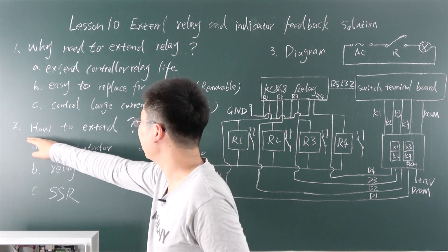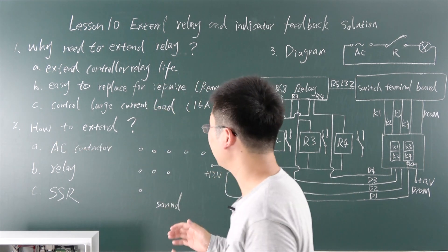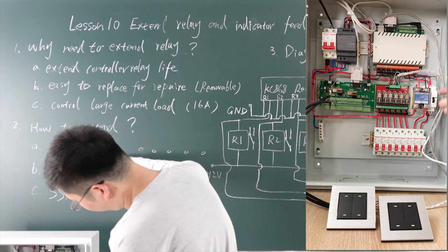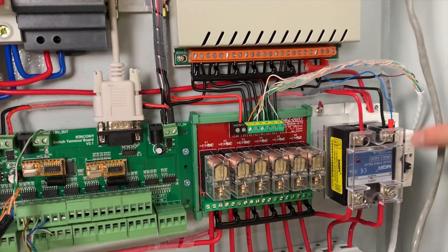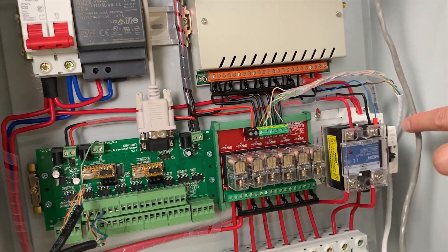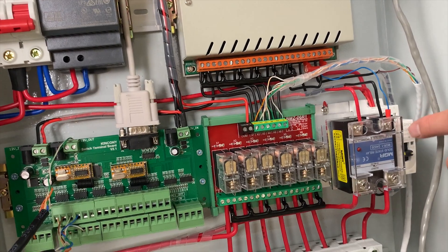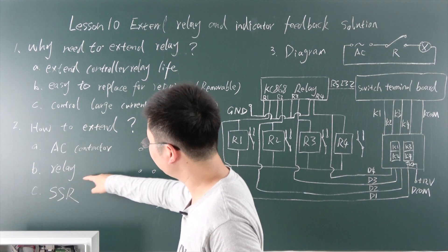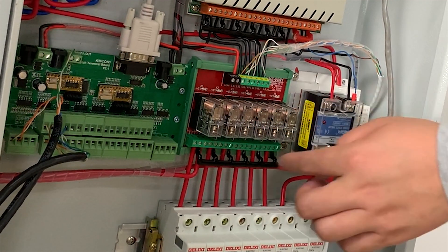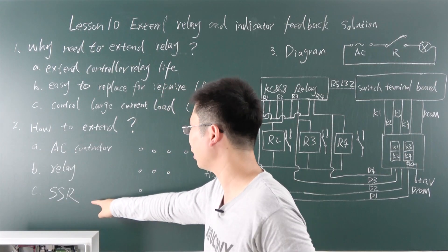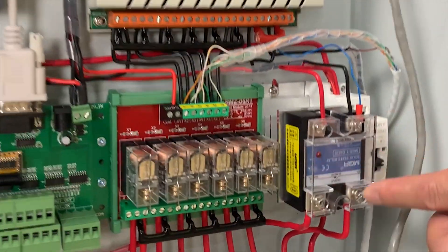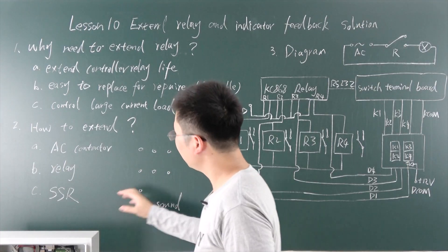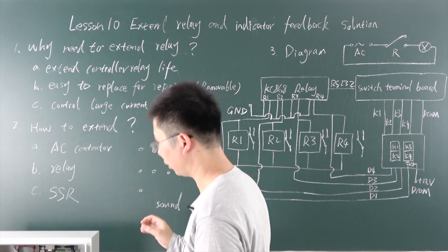Now let's look at step two: how to extend. The relay device can be extended using three types of devices. One is the AC contactor — this is a DC-controlled AC contactor that uses DC 12 volts to switch power on and off. Two is the standard removable relay, commonly used. And three is the SSR — solid state relay, here used at 20 amperes.